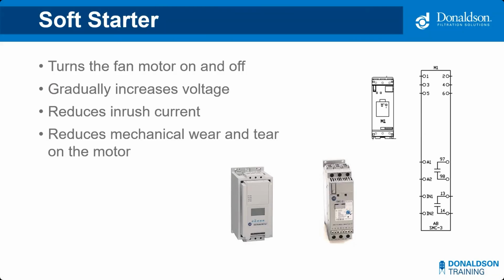Now those standard motor starters will apply that full voltage to the motor instantly, which can increase the wear and tear on the equipment and increase the peak usage with the bills from the electrical utility. To help reduce that wear and tear on the equipment, a soft starter can be used to ramp the voltage up to full voltage. A soft starter does not control the speed up and down during the operation. It only ramps the voltage while starting and stopping. It does not completely eliminate all of that inrush current, but it does significantly reduce it. We will discuss speed control with variable frequency drives later on. For now, I'll pass it back to Asa.